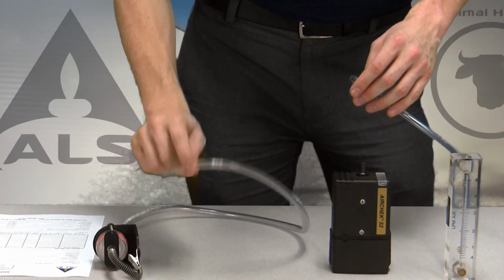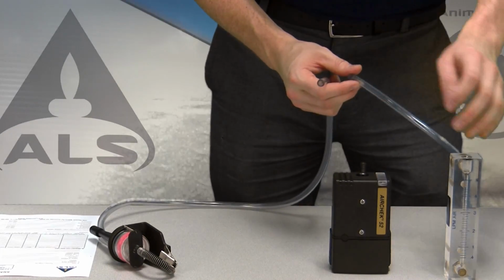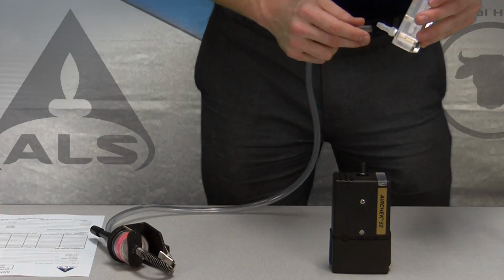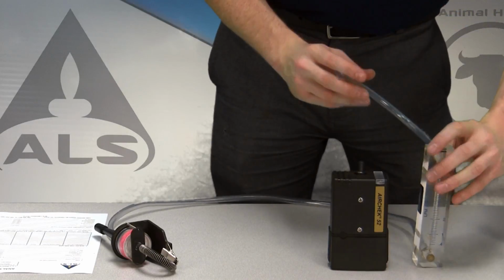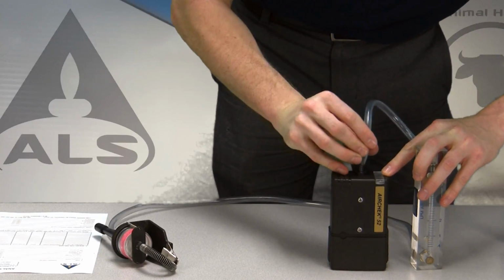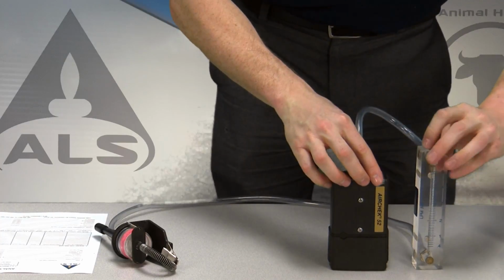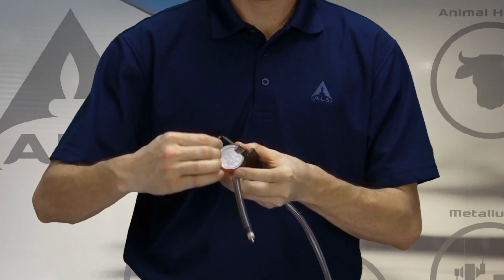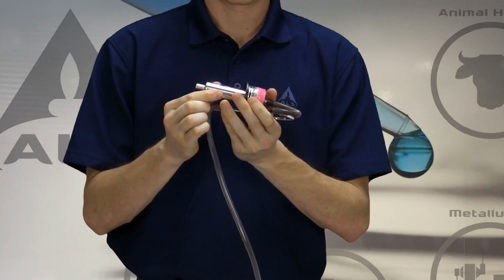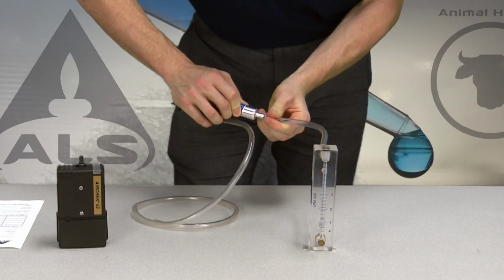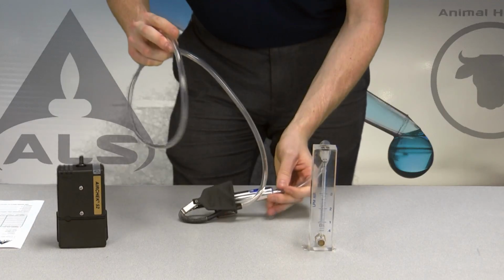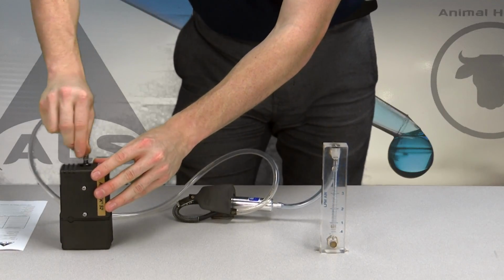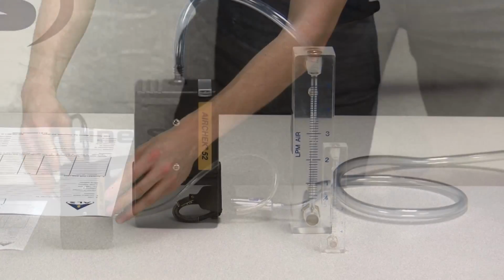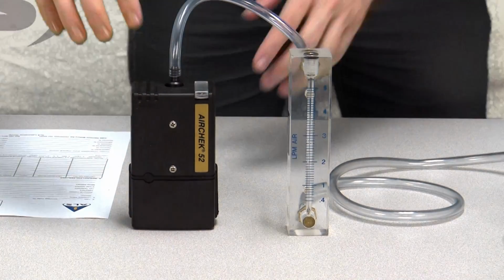Use the second length of tubing to connect the bottom port of the field rotometer to the filter cassette holder. Finally, connect the pump inlet to the tubing from the top port of the field rotometer. If you are using the aluminum cyclone, follow the same instructions. Once you have all the pieces assembled, slide the cyclone adapter over the body, then use the tubing from the top of the field rotometer to connect the inlet side of the adapter and the second length of tubing to connect the pump inlet. Make sure the field rotometer is standing upright at all times.